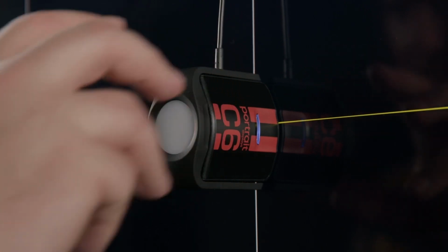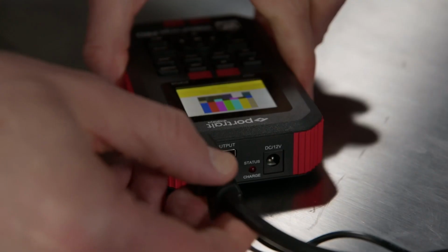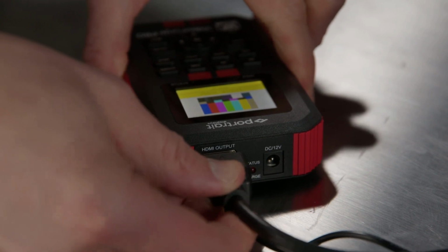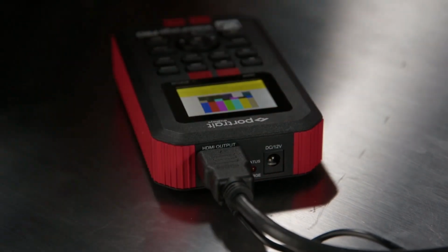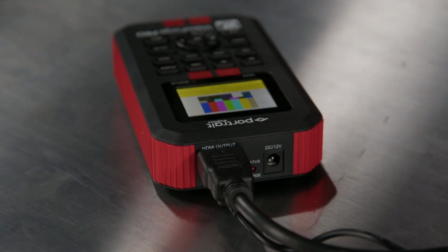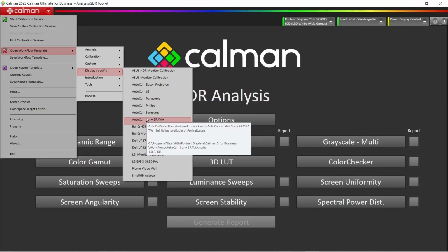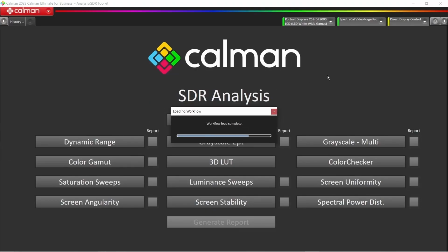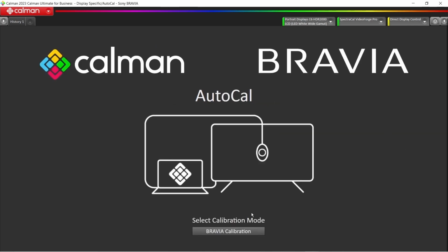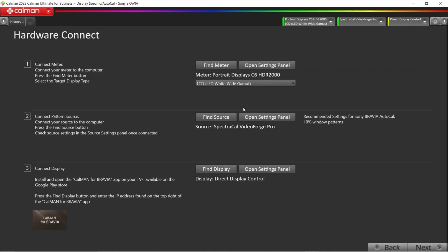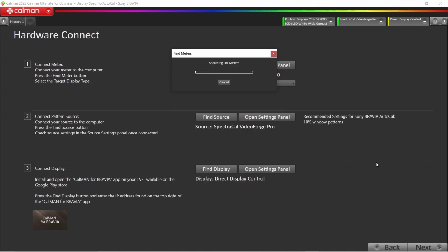The meter is connected through USB to the laptop that's running CalMan. A pattern generator is also connected to the same laptop so that the color patches are loaded directly from the pattern generator. Then you load your Sony BRAVIA display-specific workflow. With this workflow, it's a wizard that tells you step by step how to perform the calibration. So you start the workflow, connect to the meter, connect to your generator, then connect to the Sony BRAVIA display over IP. After that, the CalMan calibration software can start applying the calibration.